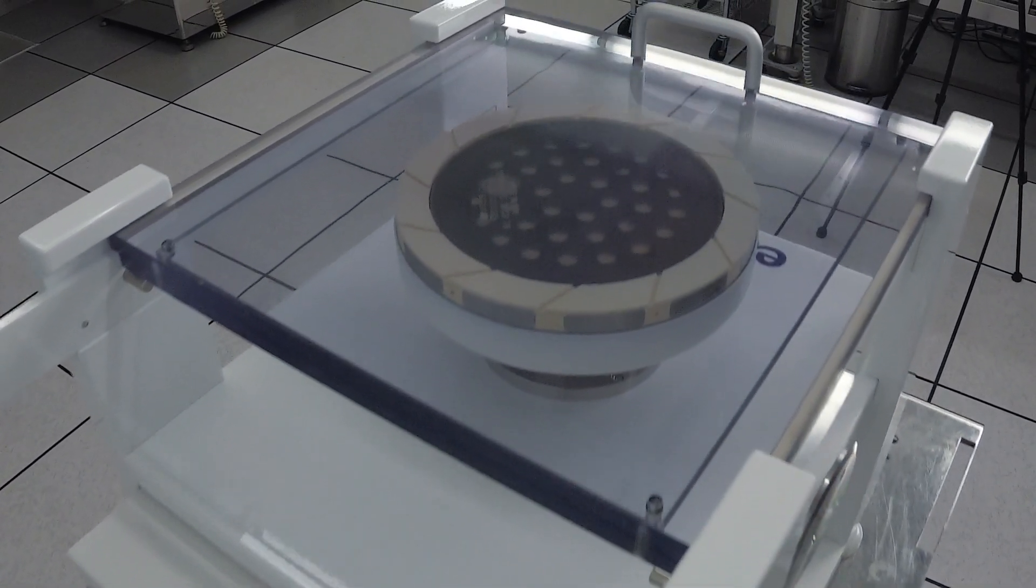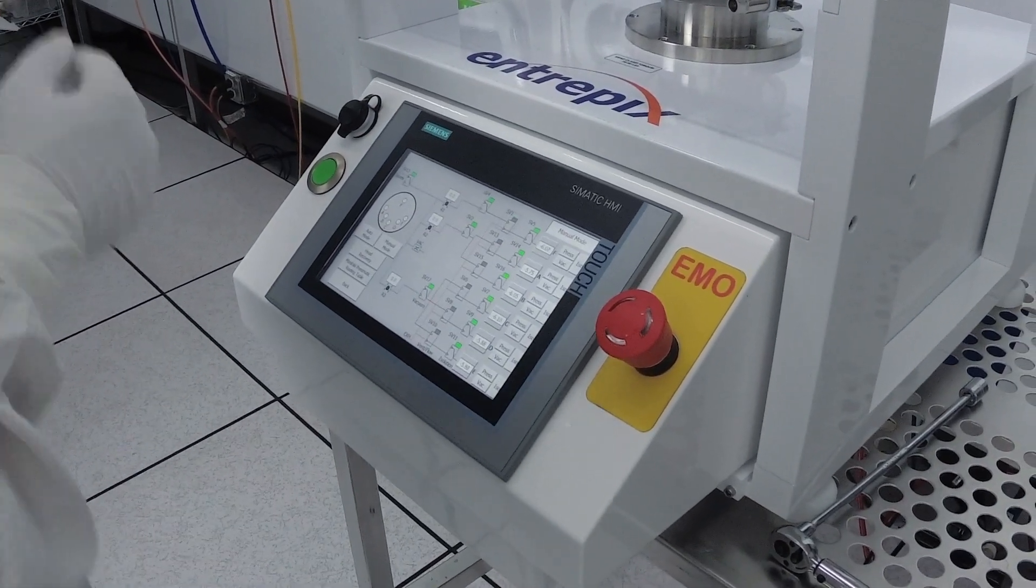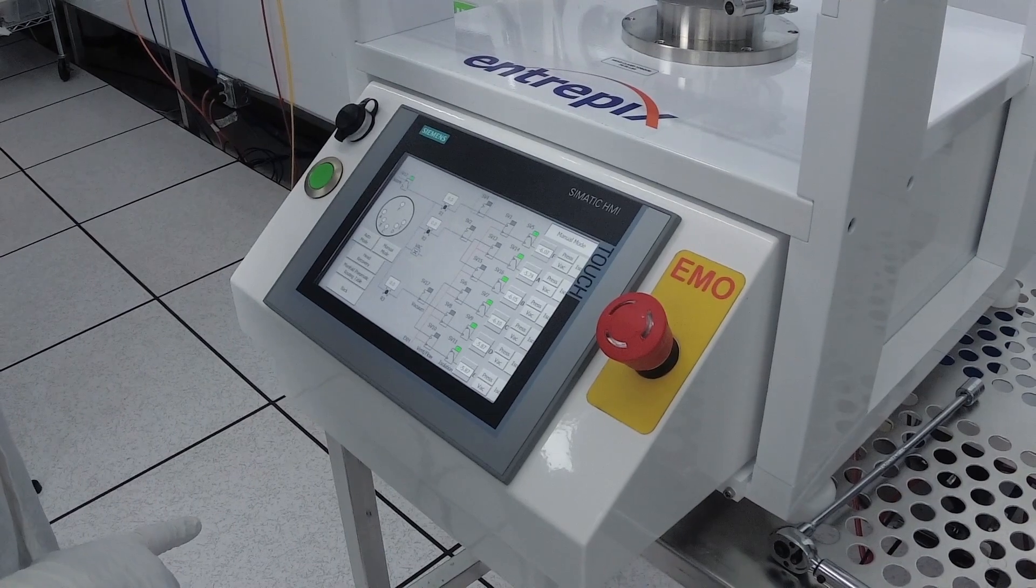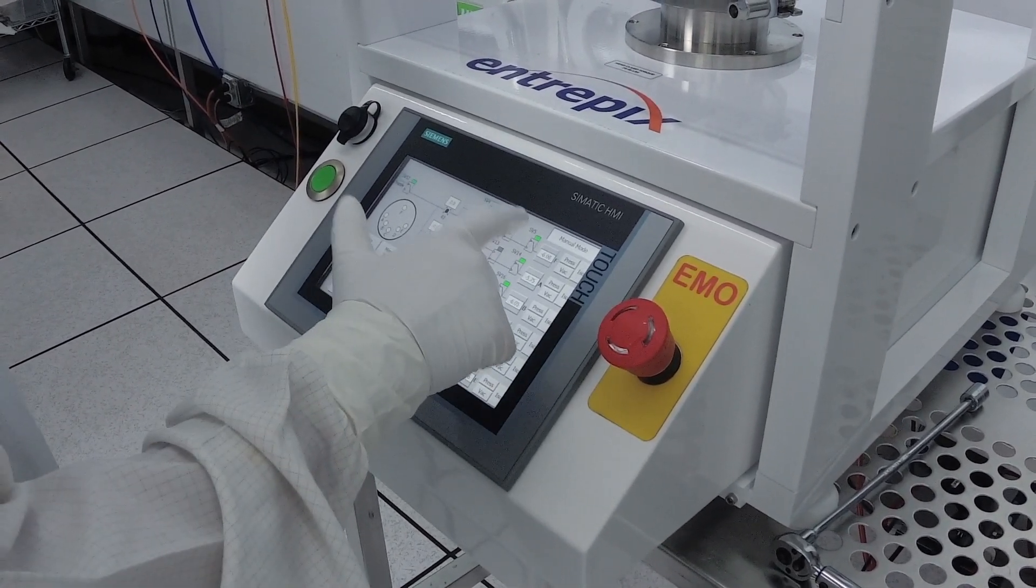One of the most powerful capabilities of the Entrepix Head Tester is the ability to operate the system in manual mode while viewing the pressures within the head in real time, providing the operator with the ability to troubleshoot and address specific concerns without running through an entire test cycle, reducing costly tool downtime.